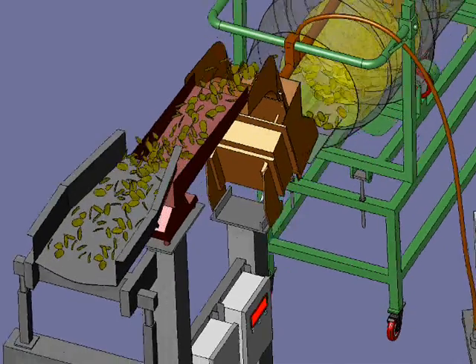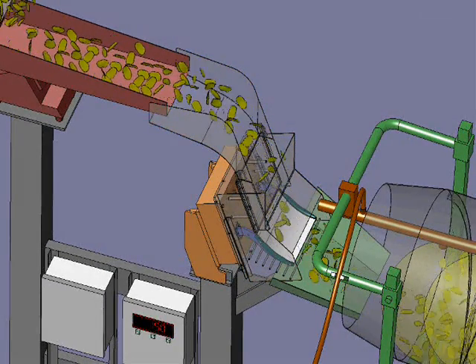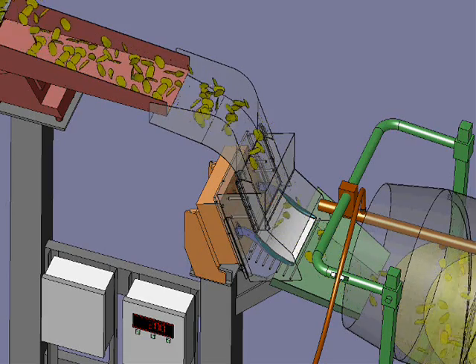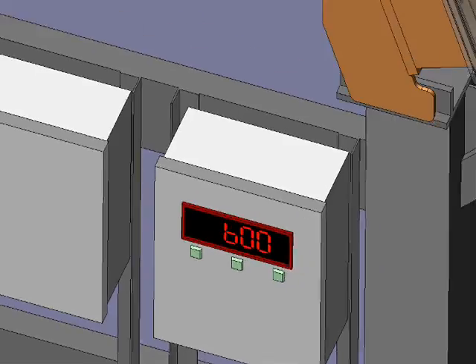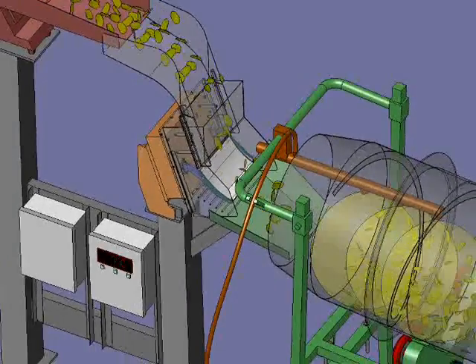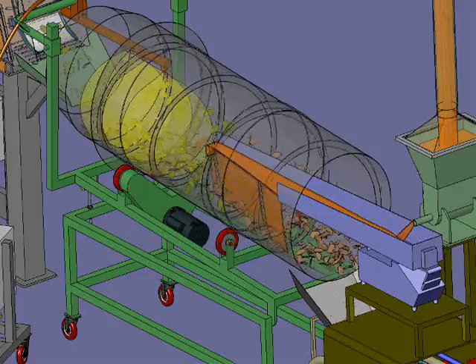The flow control output is a real-time output that can govern the flow rate. Modulating a valve with a 4 to 20 milliamp signal allows the operator to adjust variables in the process to keep flow at the required output. For example, the flow control application can allow the feeding of an extruder at a constant rate by controlling the flow rate through a rotary valve. Flow control applications include ratio control of two or more product streams, extruder feed control, and provides a continuous flow rate.